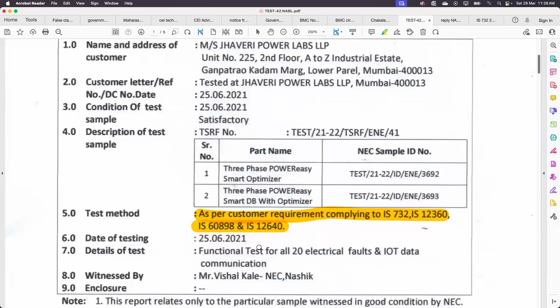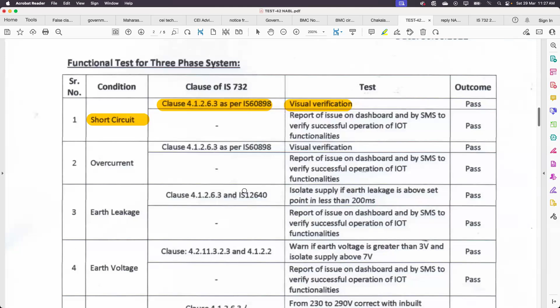If we go further, please note the laboratory has made a very clear declaration here: NABL accredited testing and calibration laboratory as per ISO 17025. This is the claim. Now, if we go through the report, it's very funny to note that the first test is the short circuit test, done as per visual verification - the engineer verified visually that this particular device is protecting against short circuit.